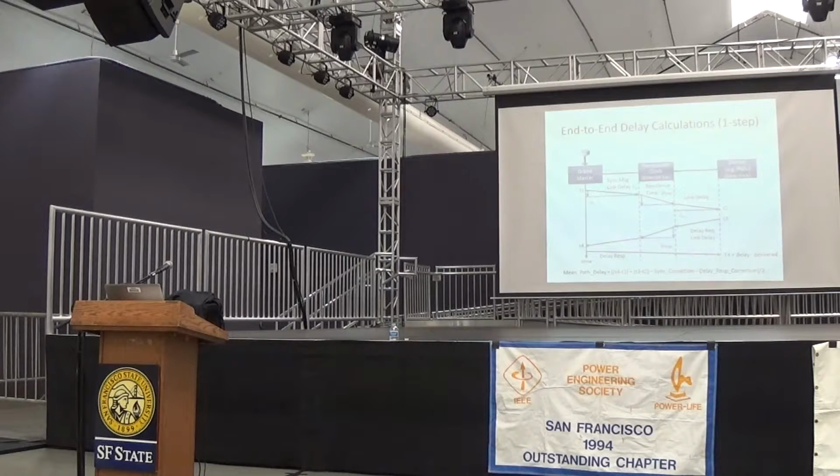Notice what you see here. When it goes through the Ethernet switch, also called the transparent clock, the transparent clock measures the residence time inside the transparent clock. And notice, it gets measured in each direction. So there's a forward delay measurement and a reverse delay measurement. Now, an interesting observation here is that this does assume that the forward and the reverse time delays are somewhat equal. What we've seen is that the variance is not that great, and so the variance is not going to affect, say, hitting 100 nanosecond time accuracy right now.